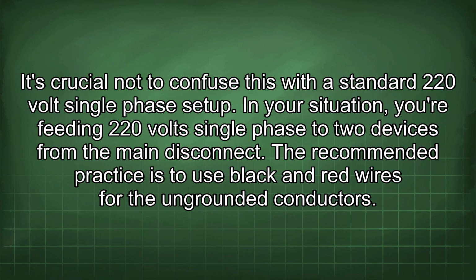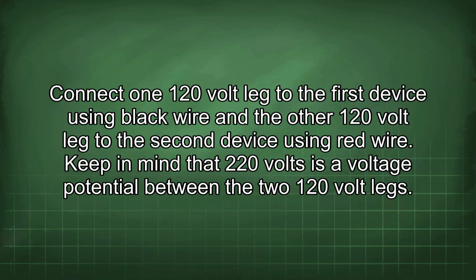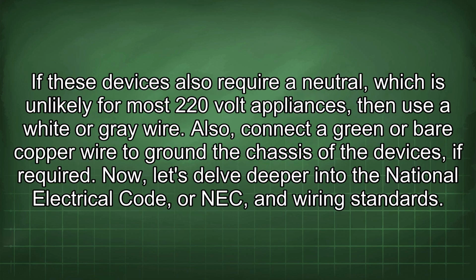In your situation, you're feeding 220-volt single-phase to two devices from the main disconnect. The recommended practice is to use black and red wires for the ungrounded conductors. Connect one 120-volt leg to the first device using black wire and the other 120-volt leg to the second device using red wire. Keep in mind that 220 volts is a voltage potential between the two 120-volt legs. If these devices also require a neutral, which is unlikely for most 220-volt appliances, then use a white or gray wire. Also, connect a green or bare copper wire to ground the chassis of the devices, if required.